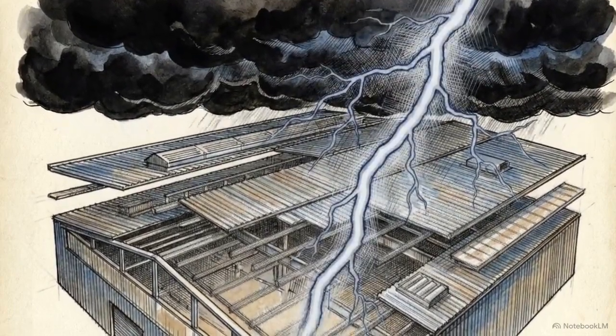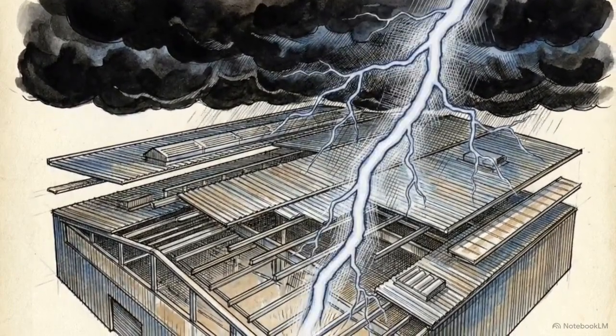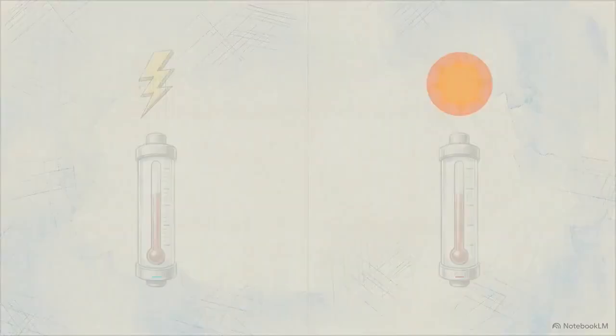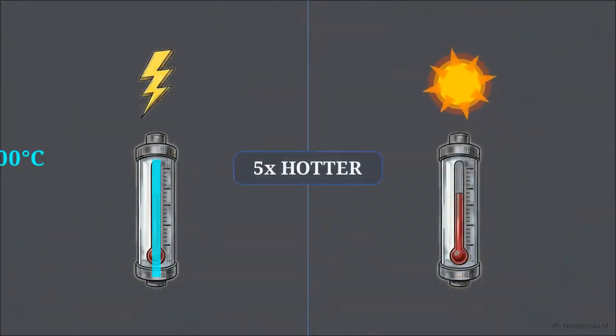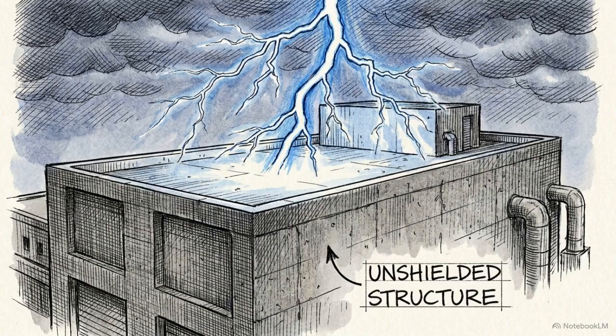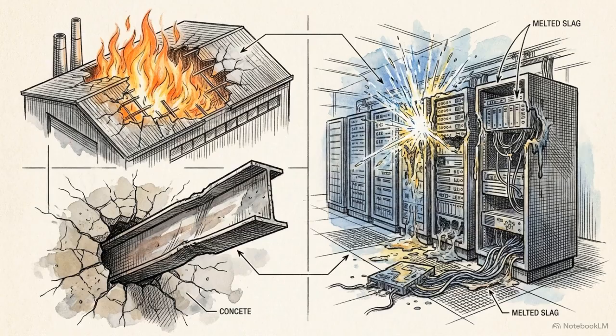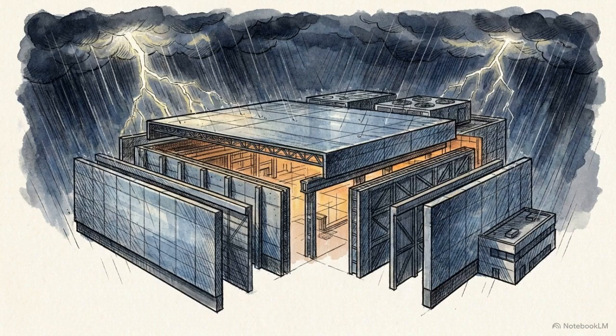A single lightning strike carries over 100 million volts of electricity and can heat the surrounding air to 30,000 degrees Celsius. That is 5 times hotter than the surface of the sun. If that kind of power hits an unprotected building, the results are immediate. It causes sudden fires, severe structural damage to concrete and steel, and instantly melts the delicate computer systems running the operation. To survive, a modern factory has to act as an invisible fortress.